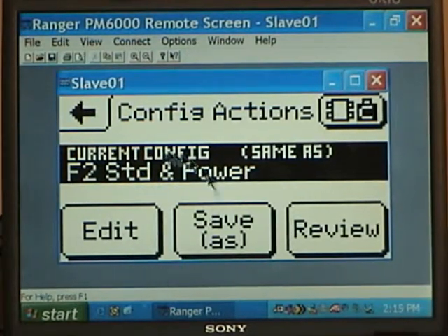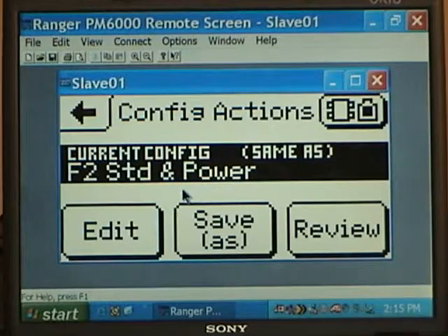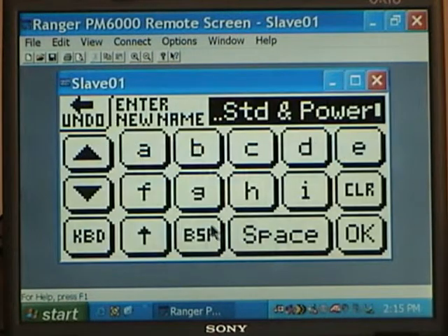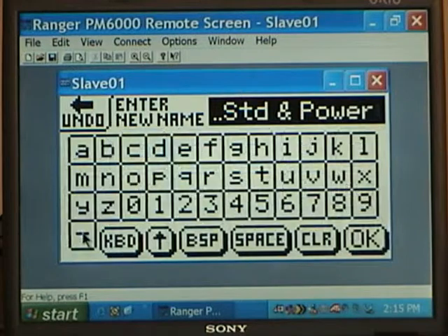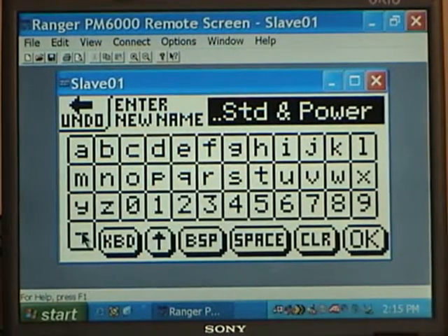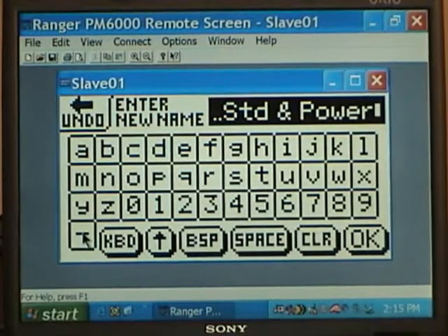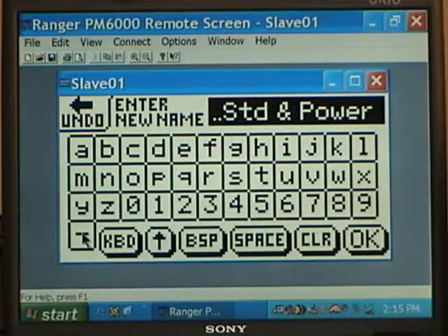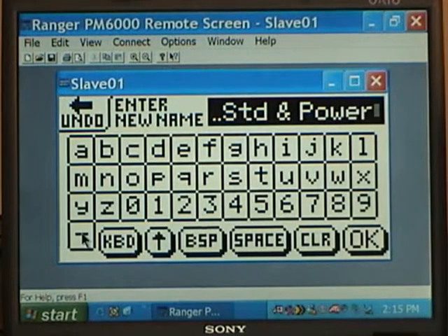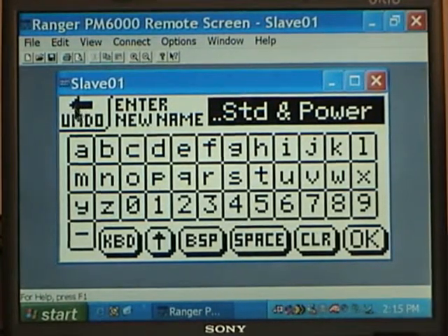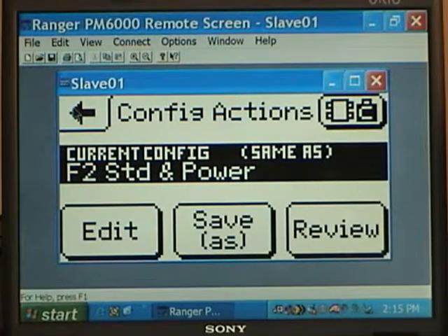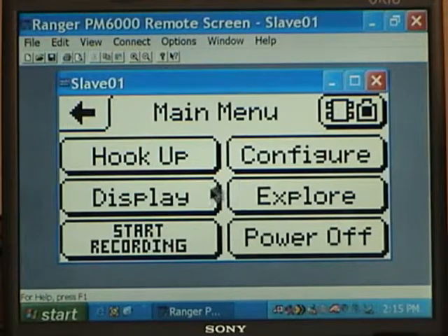Once you've got it back to this point here, if you're at a customer that is perhaps a nuisance situation that you go back to all the time, you might want to do a save as at this point, and we actually do give you a keyboard here where you can type in the name and address of the location. You might want to type in a work order number that's on your job paperwork. There could be several ways that we allow you to enter a significant name here, not some cryptic 8-character abbreviation that you have to figure out later on. Again, hitting the upper left-hand corner key takes you back one step in the programming. And we'll go back to our original main menu here.